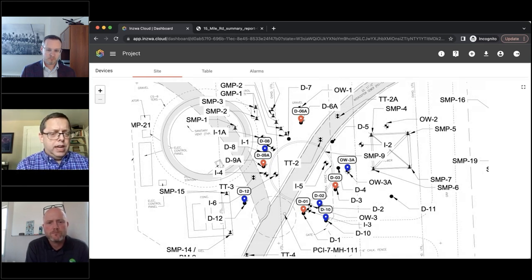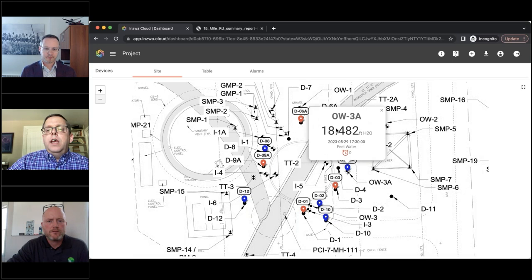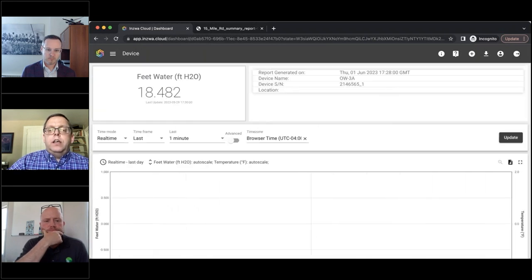In this particular case, this project is set up with a drawing showing the locations of the vibrating wire sensors that have been placed around the interceptor. We place pins on this drawing representing each of the sensors. Now you notice that some pins are in red. I believe that those sensors are currently out of service, but the ones shown here in blue are currently in service. If I click on it, I can see the latest piece of information that we have about that particular sensor.